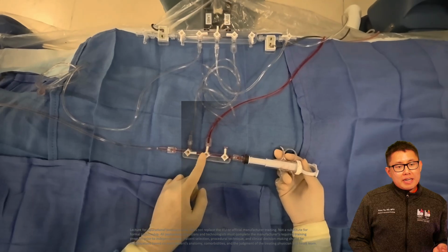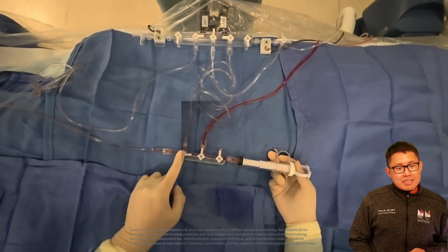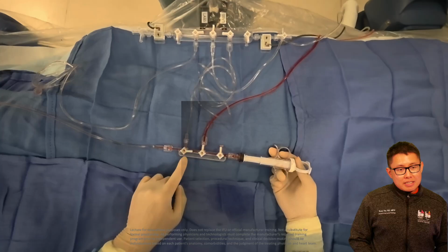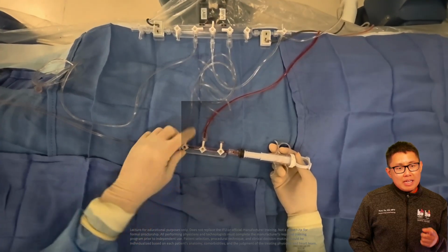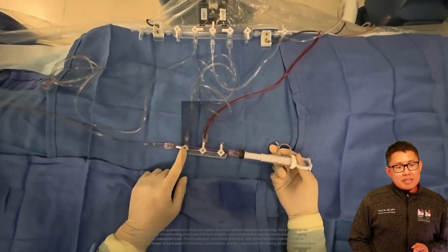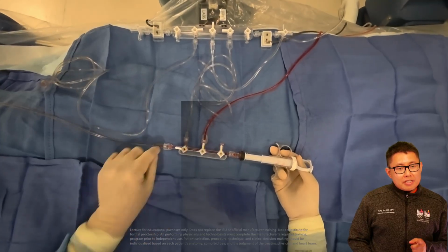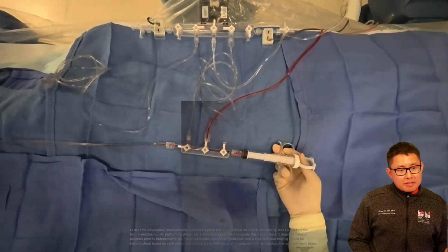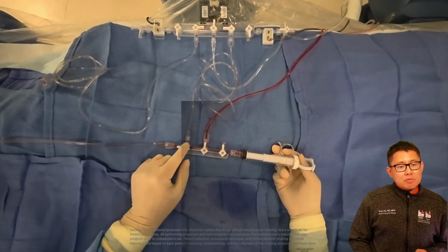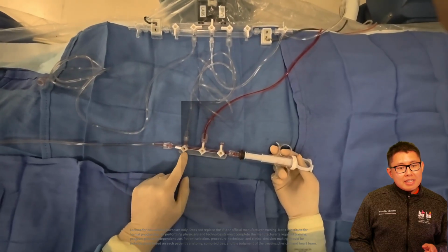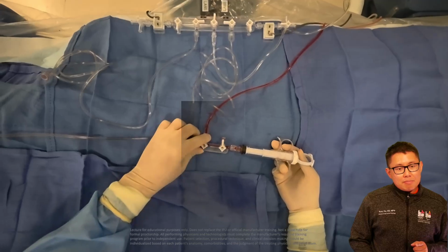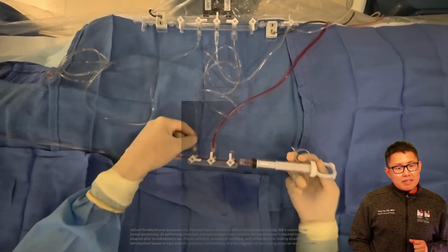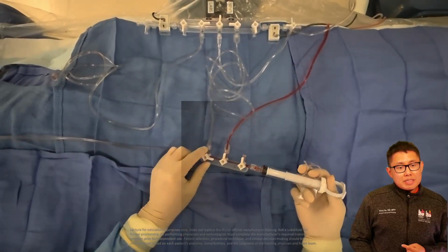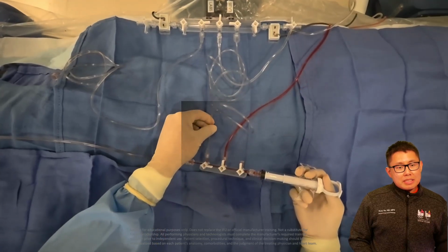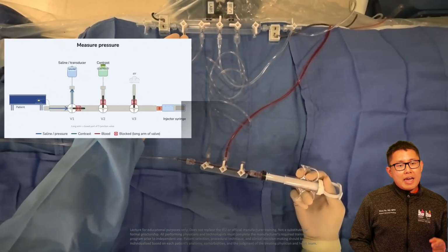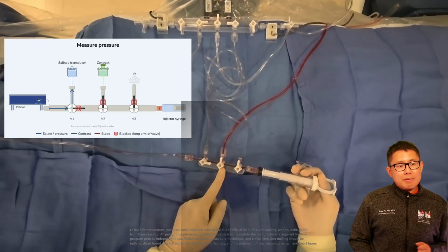So now, if I turn this knob towards the right side, there's a connection between the patient line, which is on the left, as well as the pressure sensor. Now, if I turn the long knob off to the patient, then there is a connection between the saline bag / pressure transducer as well as the injector. Because remember, the short sides are the open sides of the T valve. Now, if I have the long side pointing up, then there is a connection between the long tube connecting to the patient and the pressure transducer / saline bag. That's how we measure pressure.